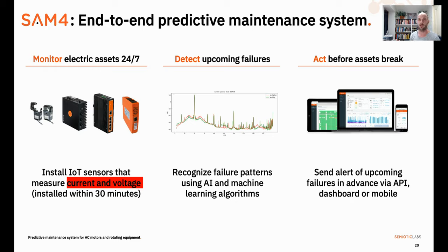The second big benefit for monitoring pumps is that it installs inside the motor control cabinet and is therefore not on the pump. So if you have a submerged pump, you don't need to install any sensors on it or close to it, which allows you to monitor that pump in a cost-effective manner. It's also a lot easier in the chemicals or oil and gas industry, where you have lots of pumps operating inside ATEX or IECEx hazardous areas, since the motor control cabinet almost by definition sits outside of that hazardous area — easy access, easy to install, without the paperwork and risks associated with working in that area.